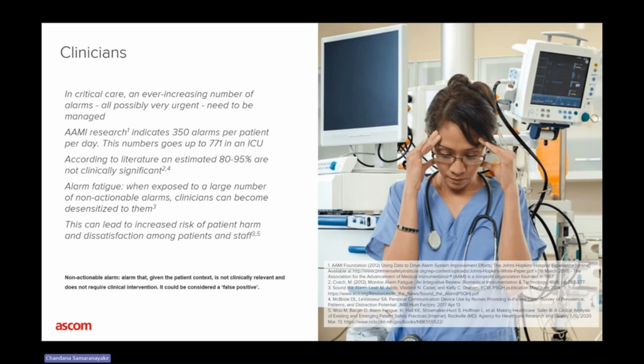So for example, let's take an infusion pump, right? When an infusion pump detects that the syringe is empty or close to being empty, it sends out a critical alert, a red alert, saying the syringe is going to empty. And it's really a critical alert if the syringe is infusing inotropes, because the moment inotropes run out, the patient starts to crash, right? It's really not a critical issue at all if the pump was infusing a bolus of antibiotics, and you can just swap out the syringe next time you walk to the bedside. But both those alarms go with the same priority, with the same urgency, but one of them is actionable and one of them is not actionable.